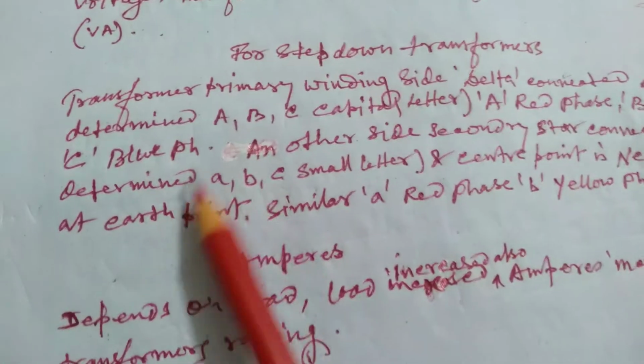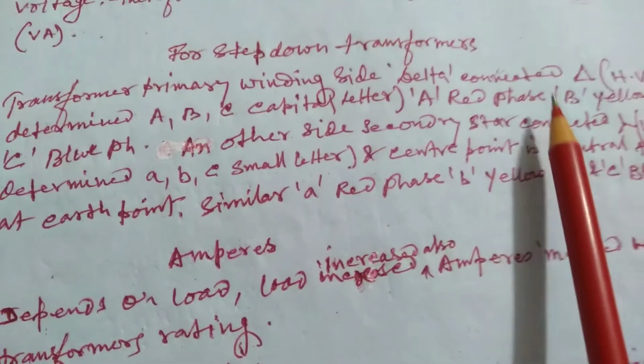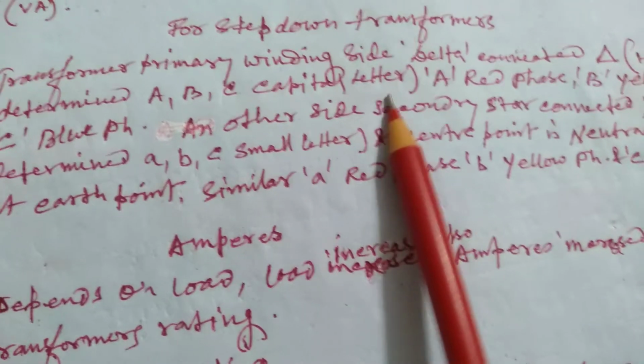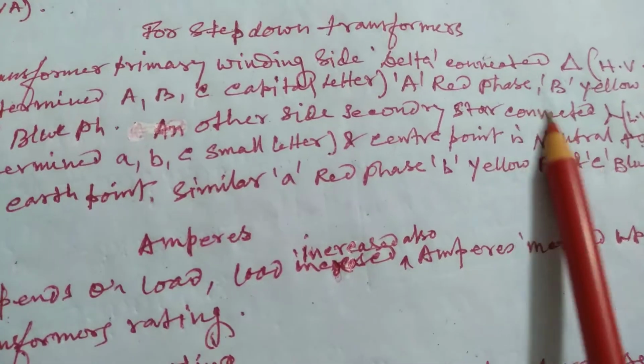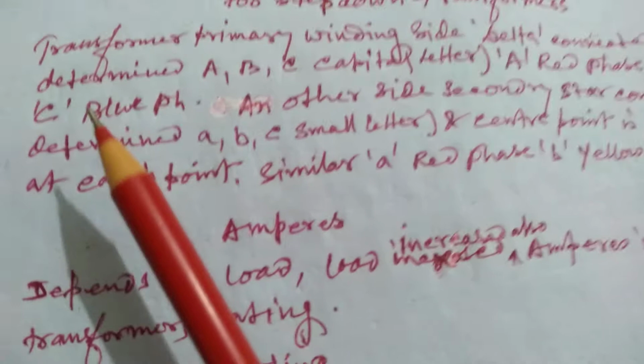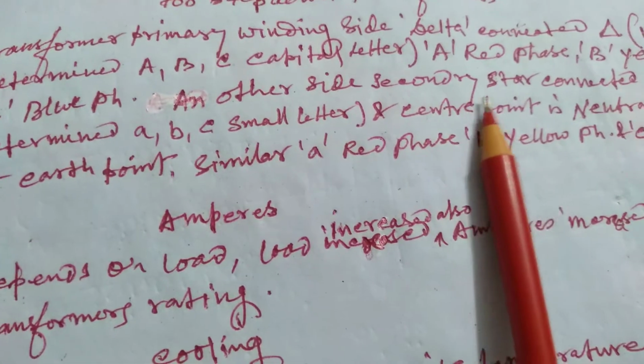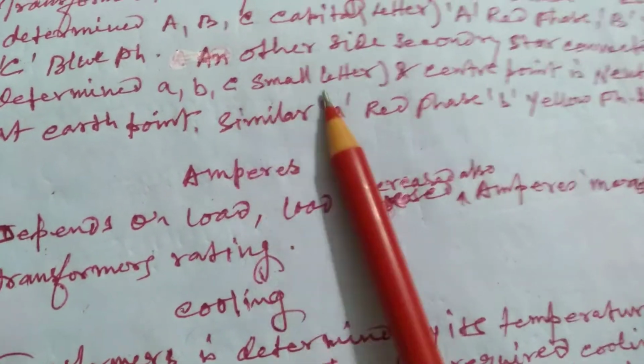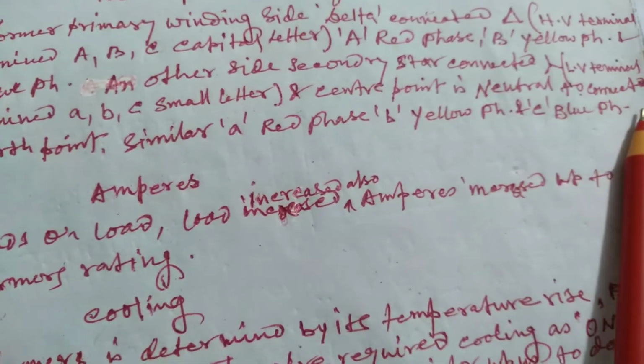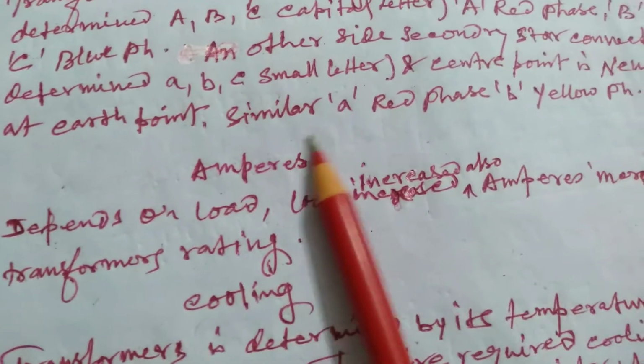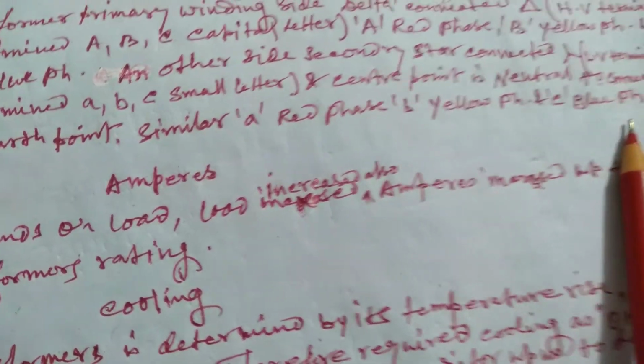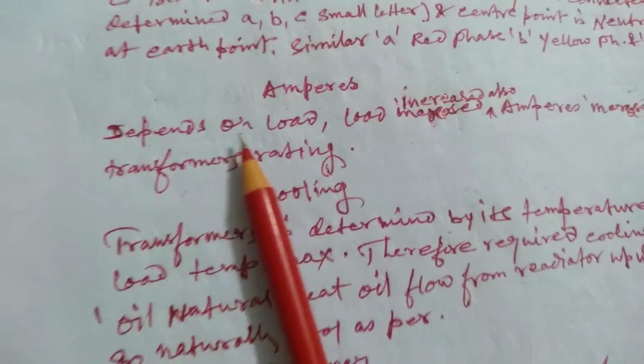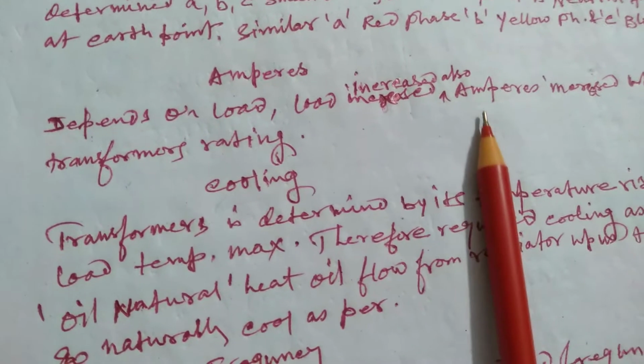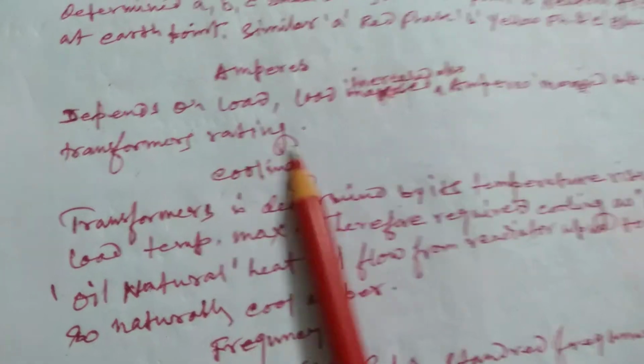For a step down transformer, the primary winding side is delta connected to the high voltage terminals, denoted by capital letters A, B, C: A red phase, B yellow phase, and C blue phase. The other side is the secondary, star connected, LV side, low voltage, denoted by small letters a, b, c, with the center tap neutral connected to the earth point, similarly a red, b yellow, and c blue. Amperes depend on load; as load increases, amperes also increase up to the transformer rating.